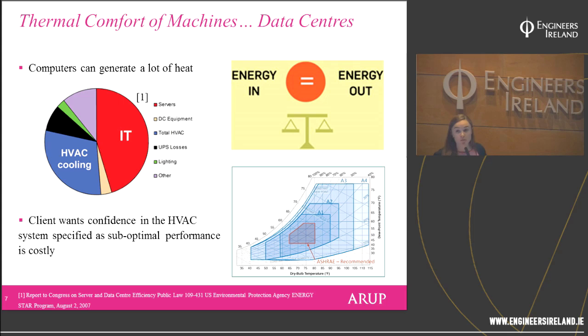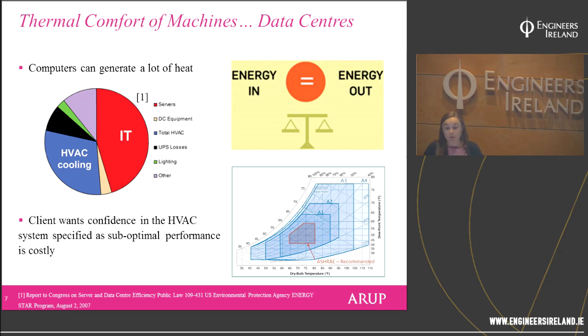Thermal comfort of machines is actually quite important, not just people. A standard computer warms up significantly during use; a whole building full of machines will get very hot very quickly. Typically, data centres are designed based on an energy-in, energy-out approach — we know how much heat is in there and therefore how much cooling is needed. But there's a lot of room for error, and the operating conditions for temperature and humidity in data centres are quite strict as per the ASHRAE codes.